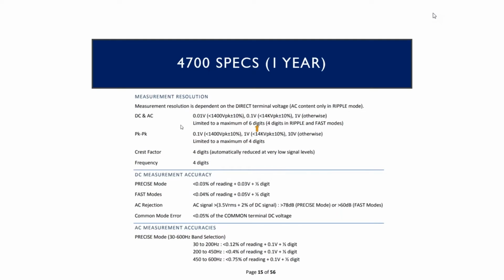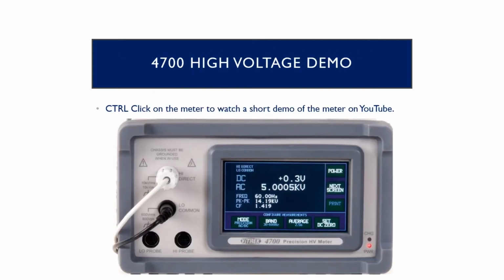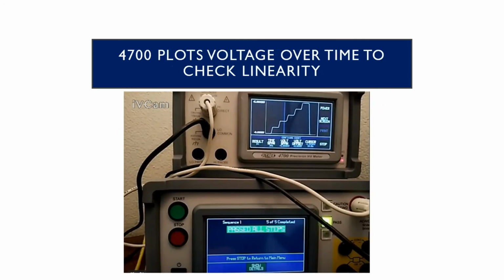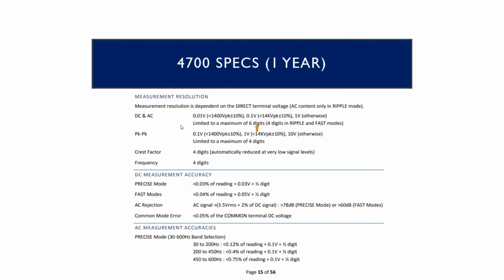These are the 4700 specs. Now, these are 1-year specs, and this goes into more detail, but to me, you can tell how good a manufacturer is by how detailed the specifications are. So if you look at a vendor and you look at an instrument and they don't put in much detail, a lot of times that means they don't understand all the different potential sources of error. We spec this out quite precisely. Typically for calibration, you would put this in the high precision mode. So that's the spec that I typically put here.